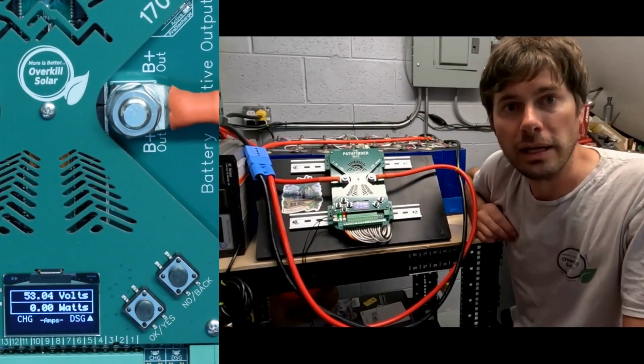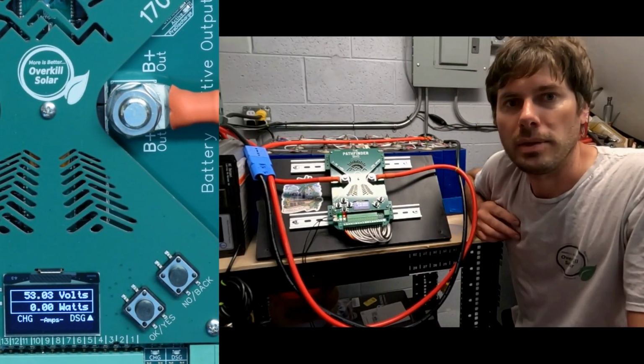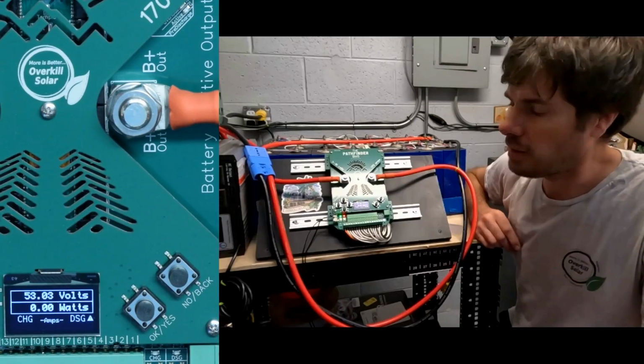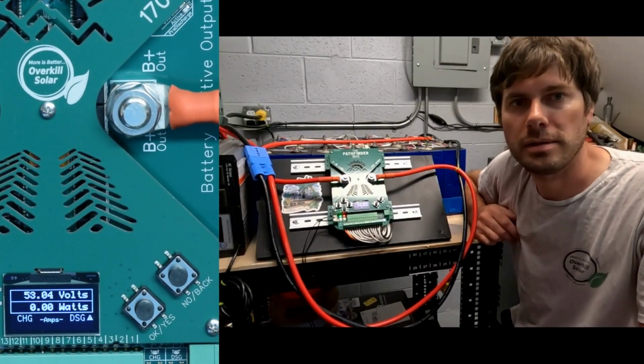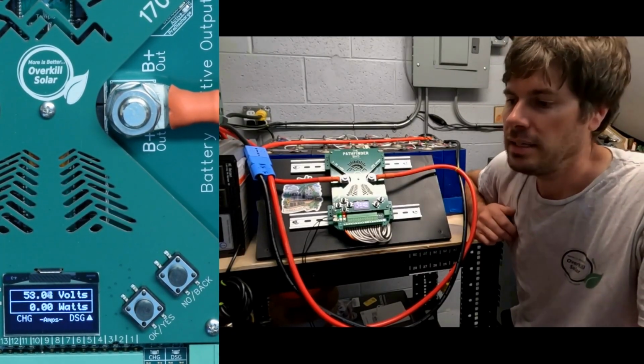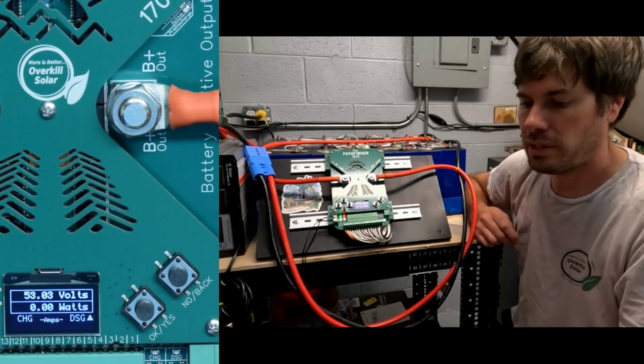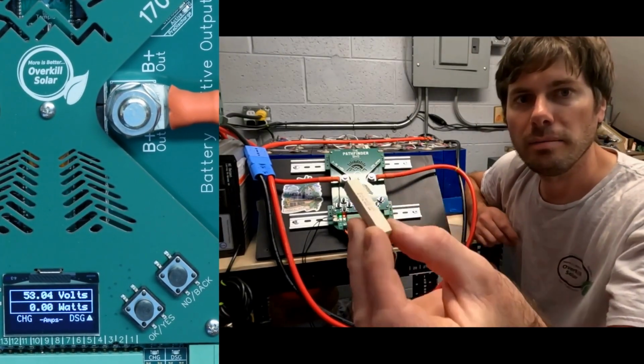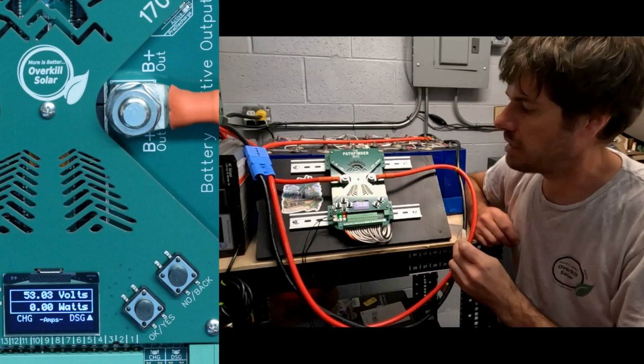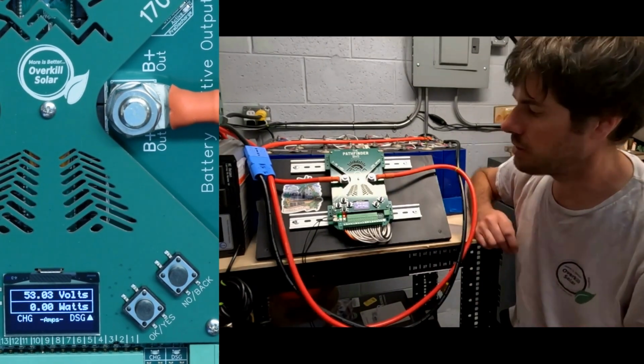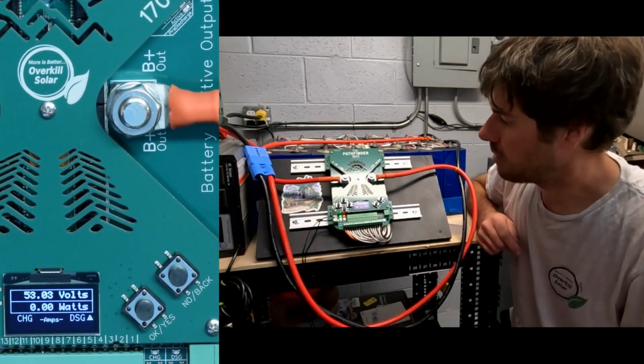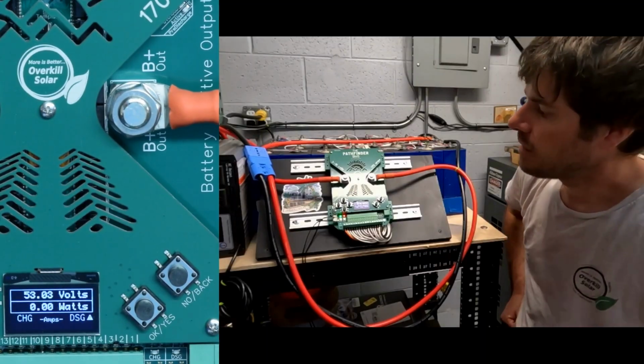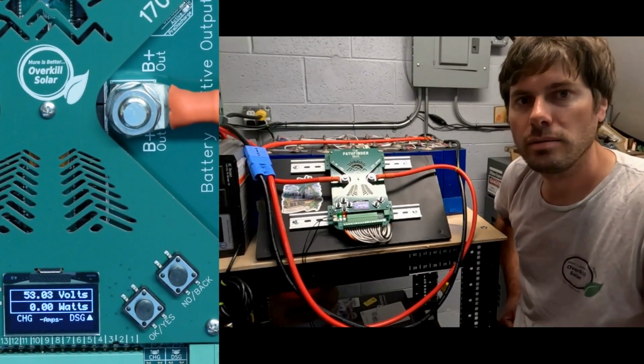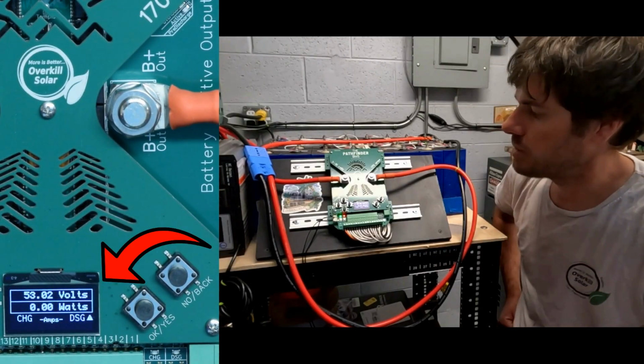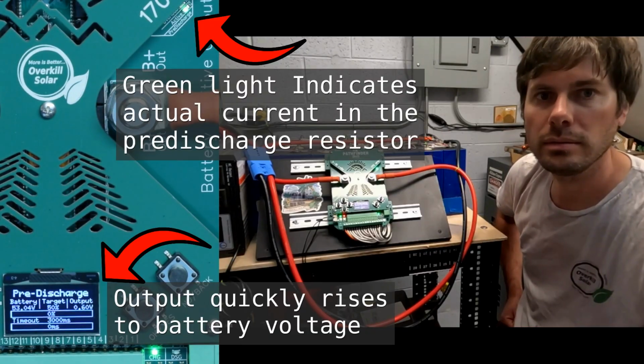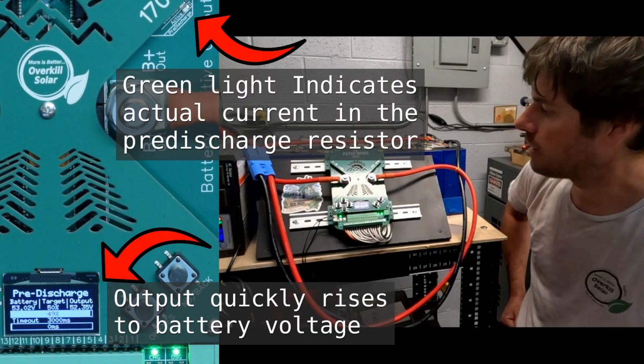Now that's normal. That'll happen with most any BMS. The large inrush current from the capacitor is going to read as a short circuit. So if you didn't have a pre-discharge circuit, you would need to manually connect a small load resistor like this in order to pre-charge the capacitors. But the Pathfinder BMS can do it automatically. As soon as the short circuit fault times out, you'll see the pre-discharge circuit become active. There it is.